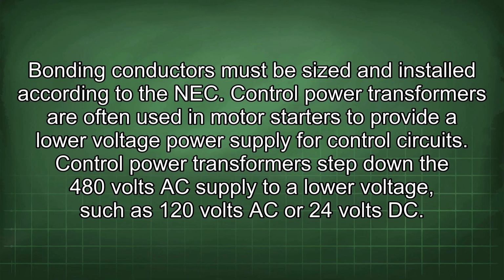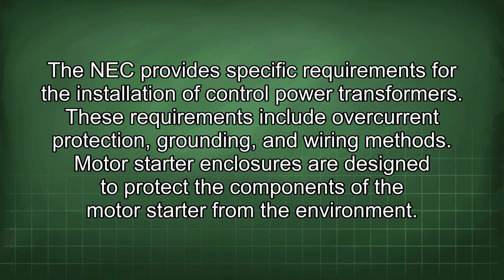Control power transformers are often used in motor starters to provide a lower voltage power supply for control circuits. Control power transformers step down the 480 volts AC supply to a lower voltage, such as 120 volts AC or 24 volts DC. The NEC provides specific requirements for the installation of control power transformers. These requirements include overcurrent protection, grounding, and wiring methods.